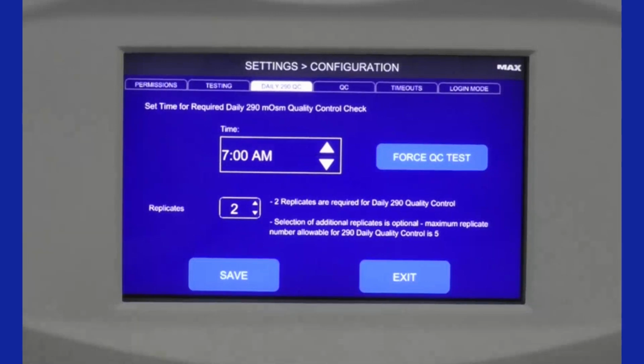Okay, so we talked about the daily Clinitrol 290 check. And it being run at the same time every day. So this is where you'll actually program that feature. So every instrument, as a default, comes with a 7 a.m. time to perform the QC. But from this menu, you can change it to whatever you want. So if you know your first shift's going to come in around 8 a.m. and perform the QC on all the chemistry analyzers in the core lab around that time, then you can program it for 8 a.m. And they can tackle it whenever they get to it.